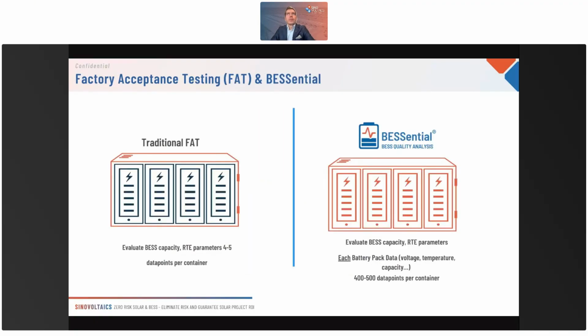But manufacturers leave a buffer on this contractual capacity, meaning that if you buy a 5 megawatt-hour container, for example, you can have a few modules inside that are not working as they should, but on an overall level the container will still pass. It will comply with the energy capacity, power, and voltage specs, but that leaves the risk of having modules and racks performing suboptimally.